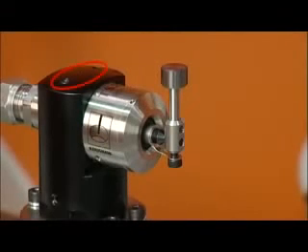Finally, check that all the mount screws are fully tightened. This prevents the stylus from moving out of alignment once aligned to the spindle axis plane. Recheck the stylus alignment after tightening.